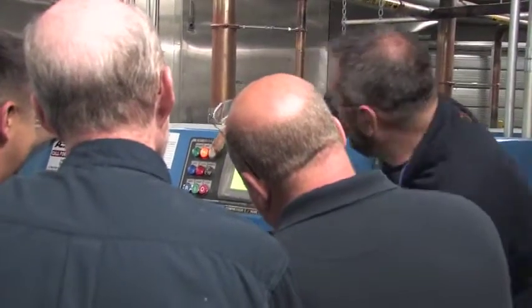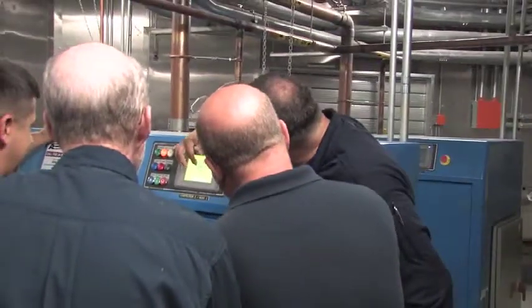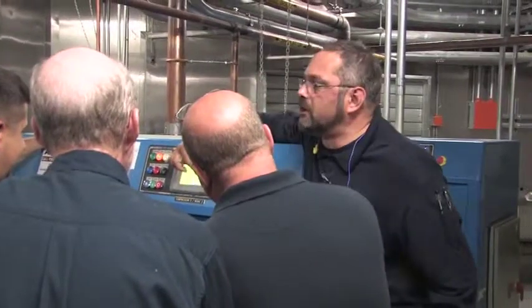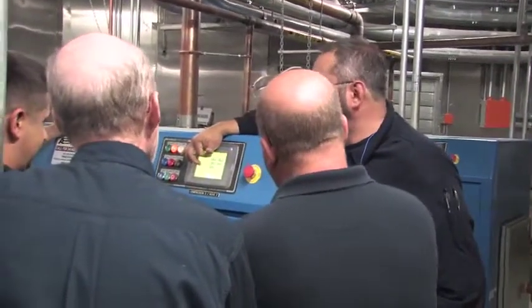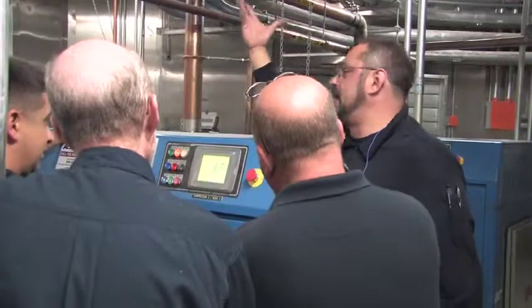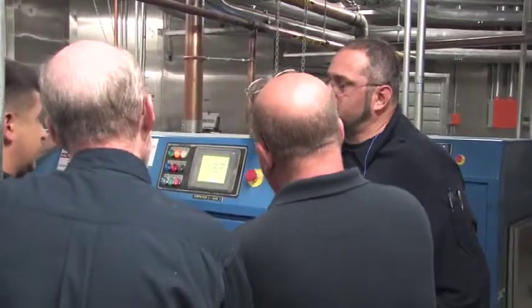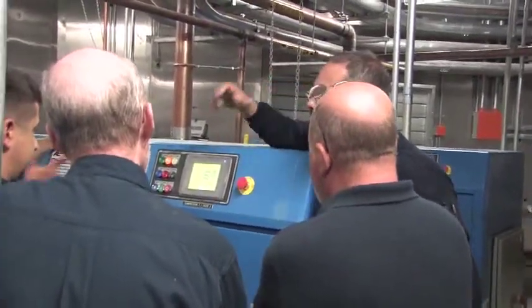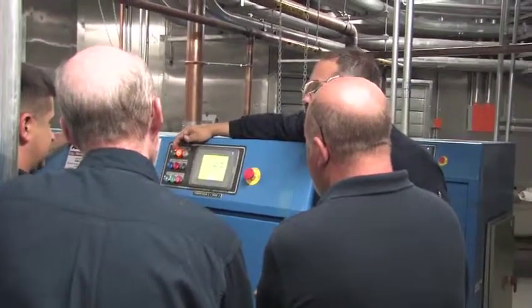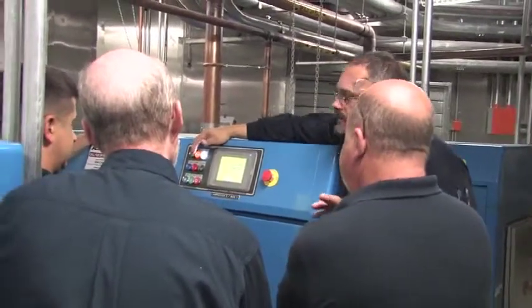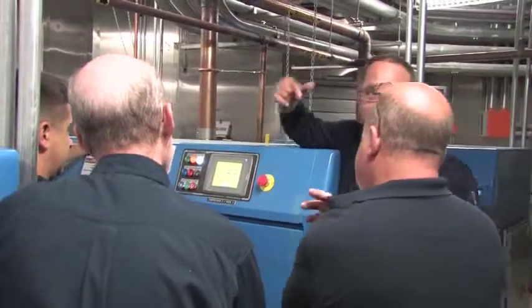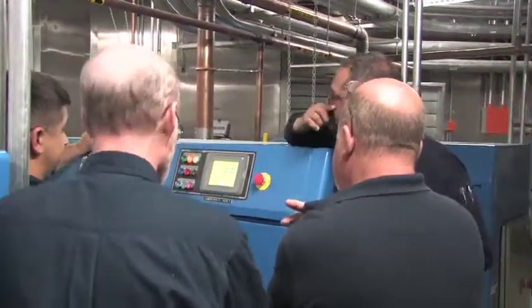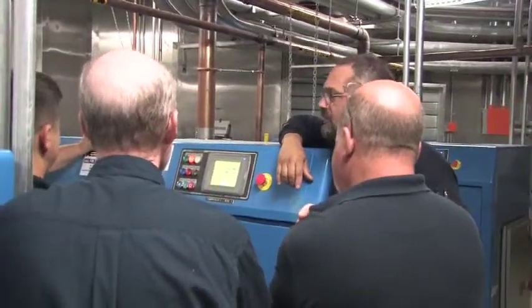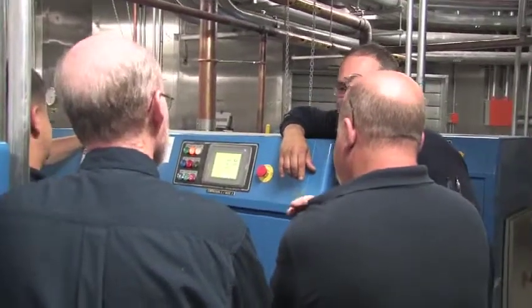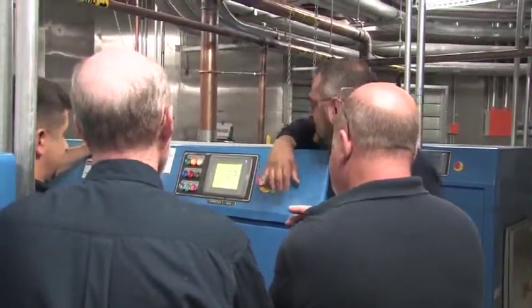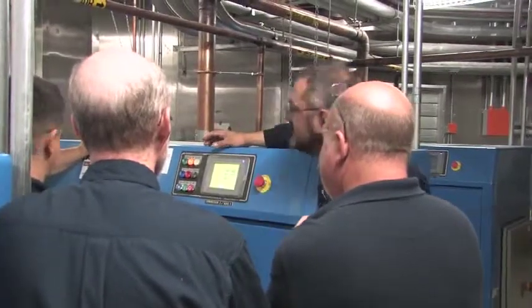Now the other stuff, lube oil. The inlet temperature will give you an alert, but it won't shut it off. There's really nothing it can do to control that. But if your inlet temperature goes over 122, it's going to warn you, because you don't want your second stage, your interstage, to be over 125. So it's coming in at that. Hopefully we're not going to be sucking in 122 degree air from outside. At least hopefully global warming isn't going to warm Boston up that much in our lifetimes. But that's really why we get this right here.